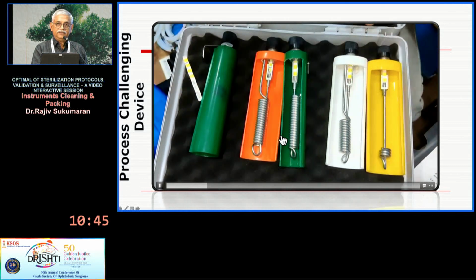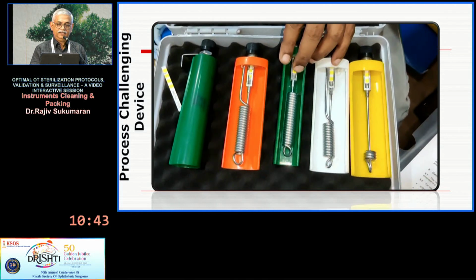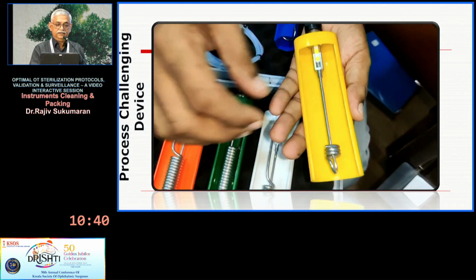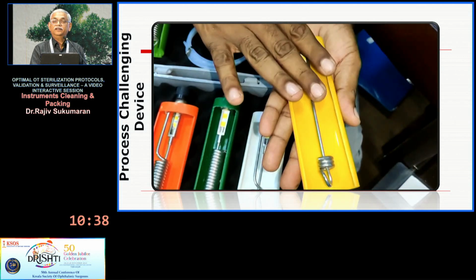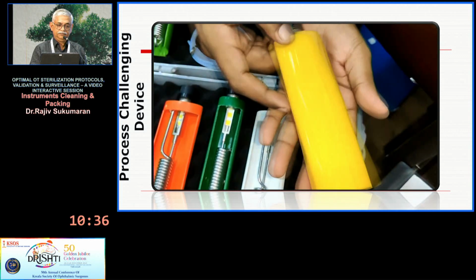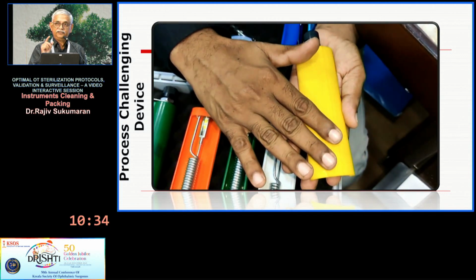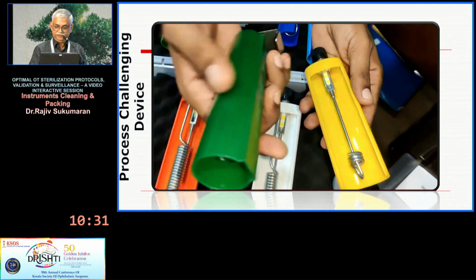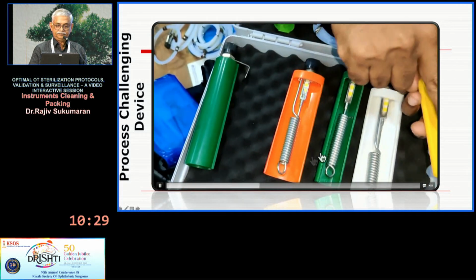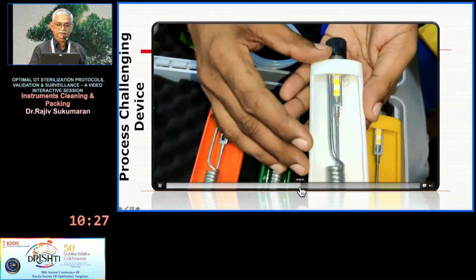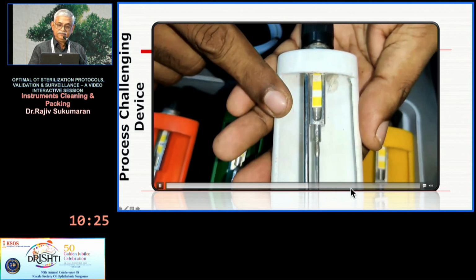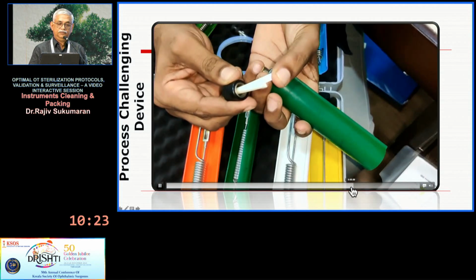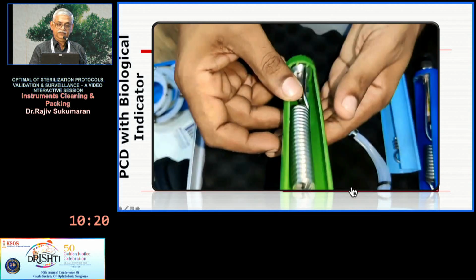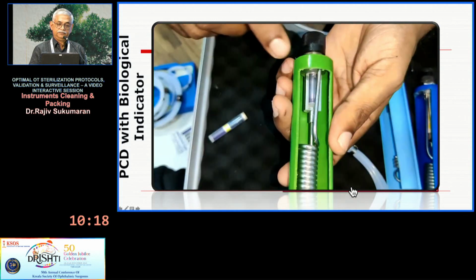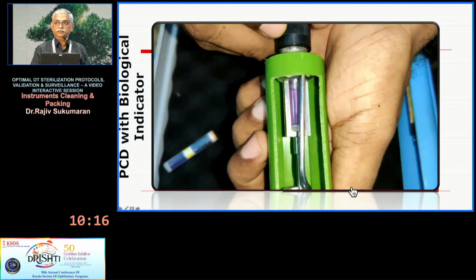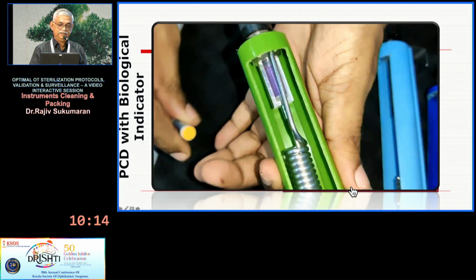These different colors are for different specialties. The yellow is for dental, the white is for general surgery, green is for ophthalmology, because the length of the inner tube, that steel tube, is different. So again this tells us the vacuum cycle in the autoclave. And you can use a biological indicator also in the process challenging device, PCD it is called.